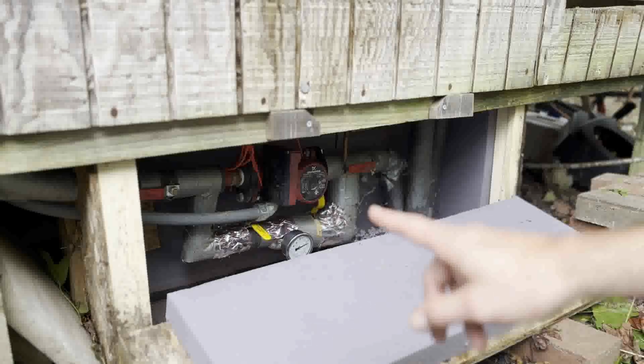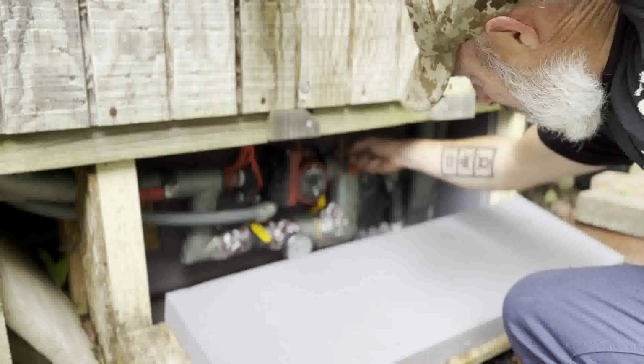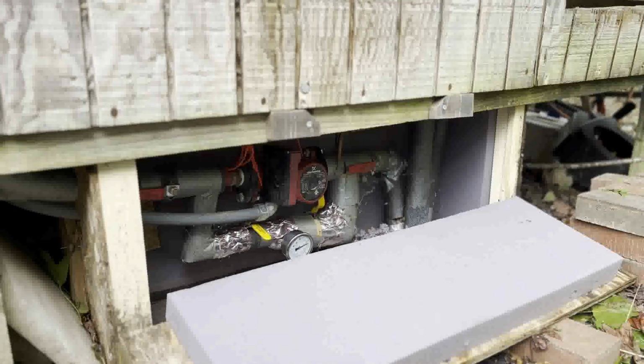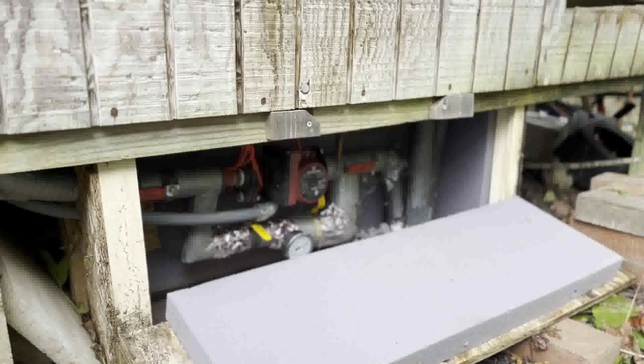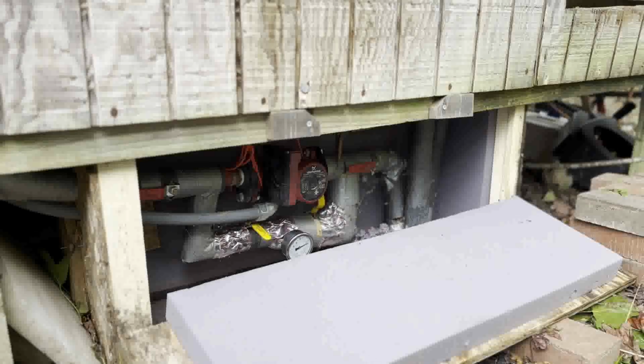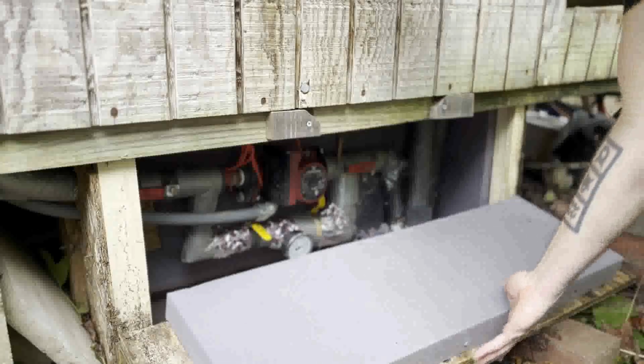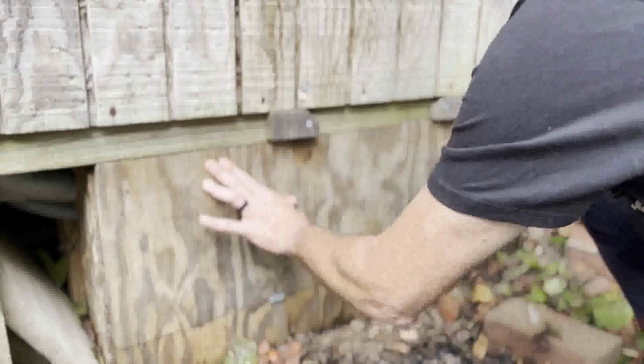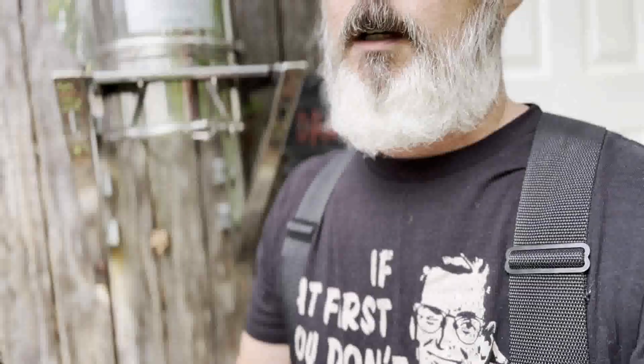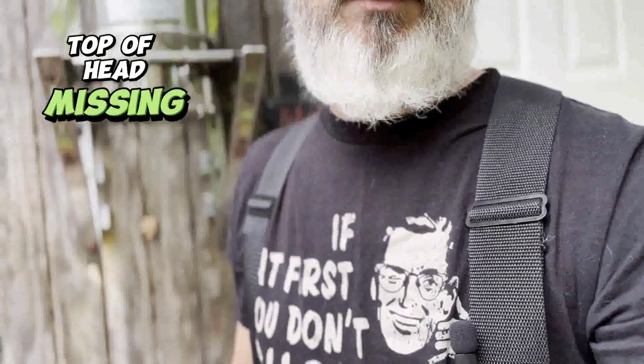There's a 60-watt light bulb in there. I don't know if you can see here. That little guy, that's a refrigerant bulb, and it's basically like an aquastat in a sense: if it gets cold, it closes a switch and turns on that 120-volt light. That's just to keep it warm in there in the event that the fire goes out and the boiler is no longer producing heat. Eventually, this pump's going to shut off, and when that happens, you've got water just sitting in a pipe that will ultimately start freezing and bust. So if the pump ever goes off and the water gets cold, that light will turn on and keep that box warm. It is insulated. It'll keep it 40 degrees down to probably 5 degrees Fahrenheit, which is way colder than we'll ever see here.